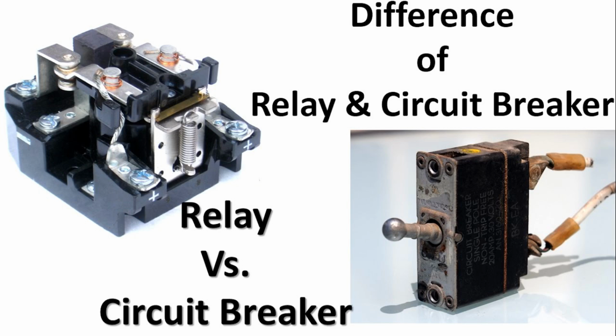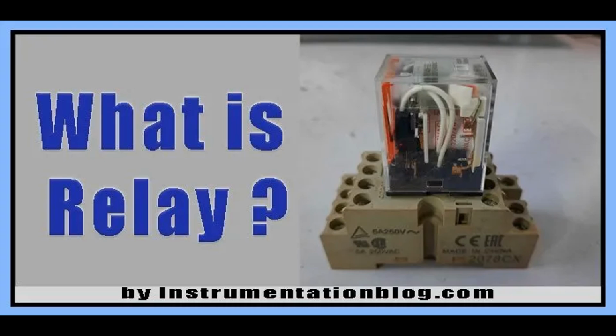Advantages. Bimetallic relays are simple in design, reliable, and cost-effective. They provide effective protection against overloads and can withstand harsh operating conditions. Additionally, they do not require an external power source for operation, as they derive their energy from the current flowing through the circuit. Limitations. One limitation of bimetallic relays is their relatively slower response time compared to electronic thermal relays. They may also have limited accuracy and repeatability, especially in applications requiring precise trip characteristics. Additionally, they may not be suitable for very high current or high-frequency applications.